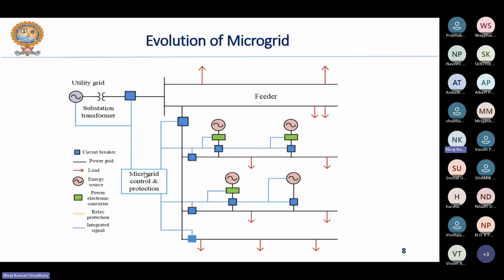Right. So there should be a central microgrid control and protection unit that is a must for the reliable operation of any power system. Suppose, for example, the fuel input to any renewable energy type source present in the system decreases, then it is obvious that the power generated by that particular DG will decrease. So that DG, which was earlier fulfilling a certain amount of load demand, will now not be able to fulfill that much of the load demand.